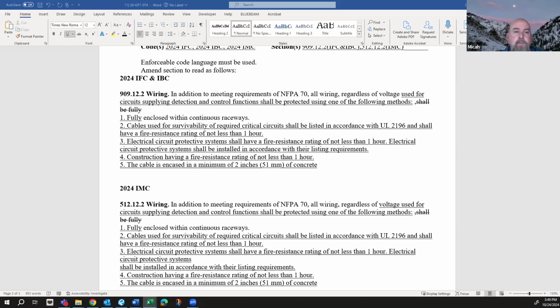I guess my question would be on item 2 of the list. It says cables used for survivability. I didn't know these cables or these circuits were required for critical circuits. When you go to that same language in 909.20.6, that is the same UL listing, but it's for a 2 hour rating, not a 1 hour. And so I'm curious how you're pulling that 1 hour and where that came from. Is it just that's where we're going to jump down to?